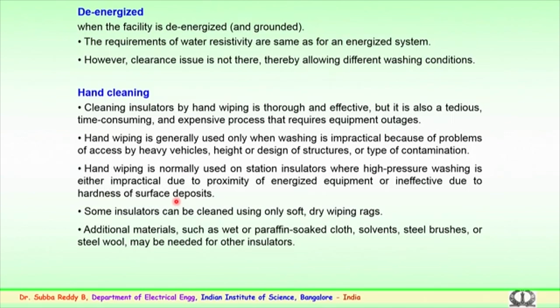If there are hard surface deposits on the insulator surfaces, it could be on the post insulator or any of the bushings, where normal washing by pressure washing cannot clean them. In such cases the hardness of the deposited material has to be dealt with by hand cleaning methods. So, some insulators can be cleaned only using soft or dry wiping rags. In some cases you may require the hardness of the surface deposit to be removed, so additional materials such as wet or paraffin soaked cloth are used. Various methods have been formed, and a few are being discussed. So, some are wet or paraffin soaked cloth, solvents, sometimes steel brushes. Again, all this cannot be generalized, and these things cannot be used for all types of insulating materials.